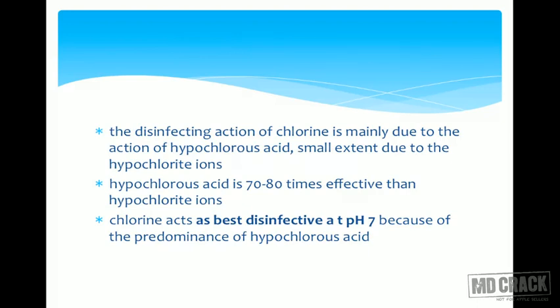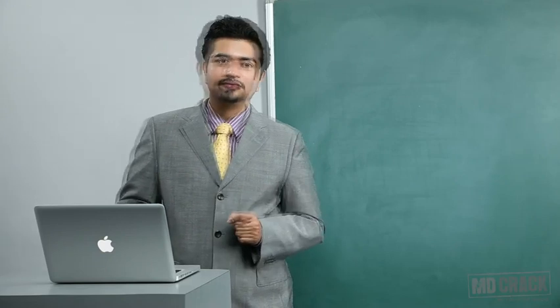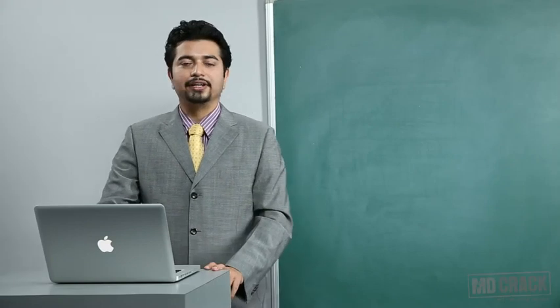Hypochlorous acid is a very good disinfecting medium, and the hydrochloric acid reduces alkalinity and helps it. The disinfecting action of chlorine is mainly due to hypochlorous acid, and only to a very small extent due to hypochlorite ions. Hypochlorous acid is 70 to 80 times more effective than the hypochlorite ion. Chlorine acts best as a disinfectant when pH is about 7 because there is a predominance of hypochlorous acid — that is the active agent in the chlorine reaction.